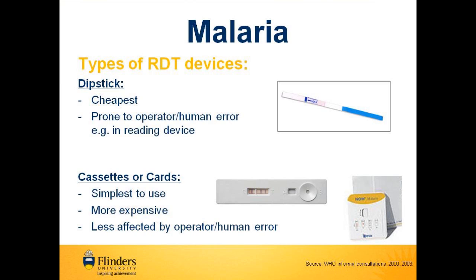There are three types of RDT devices. The cheapest is the dipstick, which works by placing the nitrocellulose strip into a well containing the blood. If the malaria parasite is present in the blood, conjugated antigen will attach to the immobilised antibody in the strip and a colour change will occur. Dipsticks are often more prone to operator error because they rely on the operator being able to read the colour change in the correct area, which can sometimes be difficult to see as there are no markings to indicate the reading window. The line can also sometimes be quite faint, but still indicate a malaria infection.